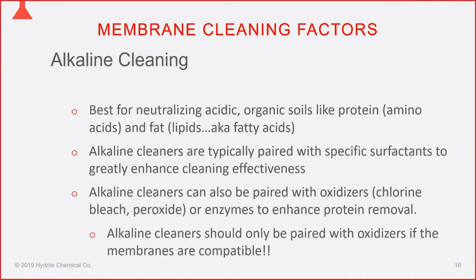Alkaline cleaners are used to neutralize acidic soils. Organic soils — proteins (made of amino acids) and fats (lipids, whose building block is fatty acids) — are acidic in nature and are neutralized with caustic or alkaline cleaners to make them soluble. Alkaline cleaners are generally not used by themselves; additives are added to enhance their effectiveness. To an alkaline wash you can add surfactant, chlorine or other oxidizers (on UF and MF membranes), or enzymes if membranes can't tolerate oxidizers.